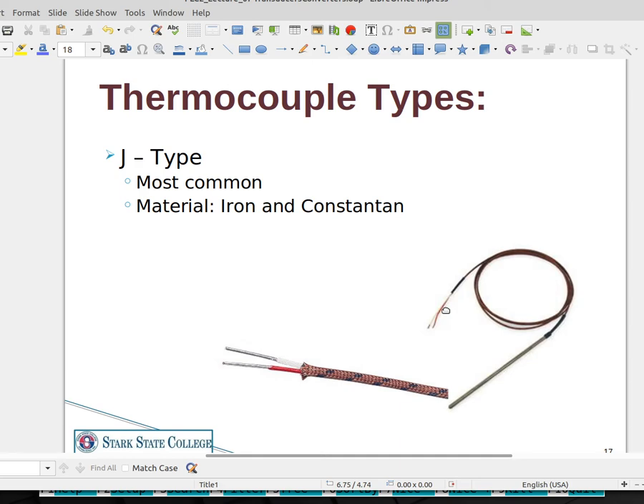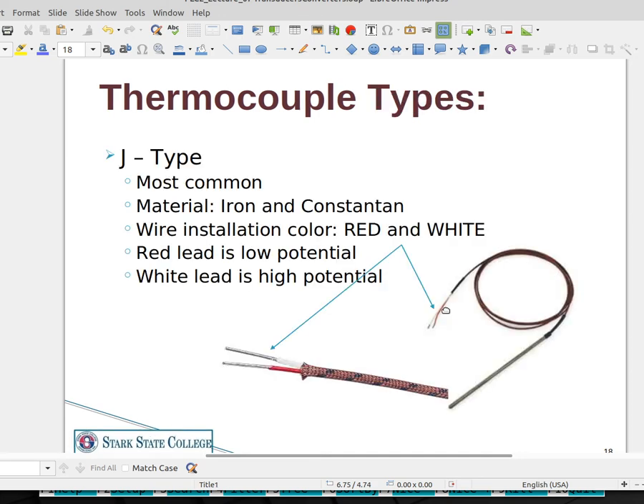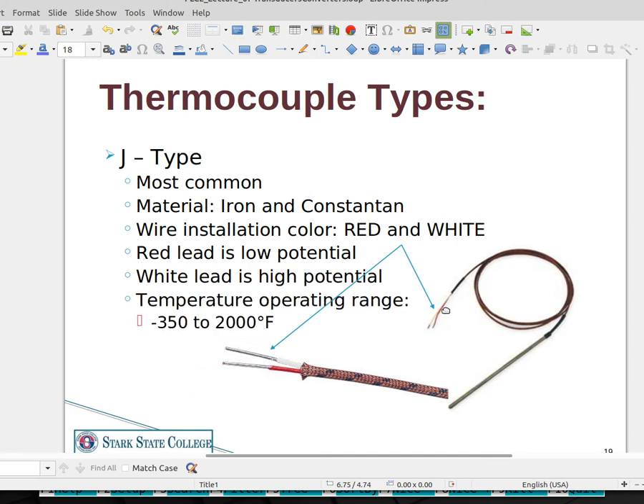The most common type of thermocouple is the J-type, which is iron and constantan. Most manufacturers use two wire leads — one red and one white. The red lead is the low potential and the white lead is the high potential. The temperature range for J-type thermocouples is very wide, from minus 350 degrees Fahrenheit all the way up to 2000 degrees Fahrenheit.